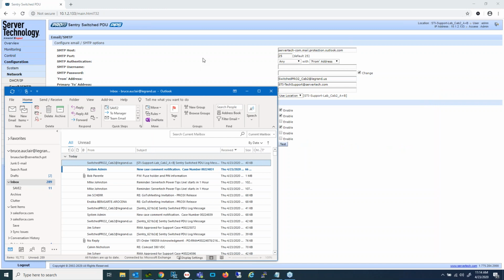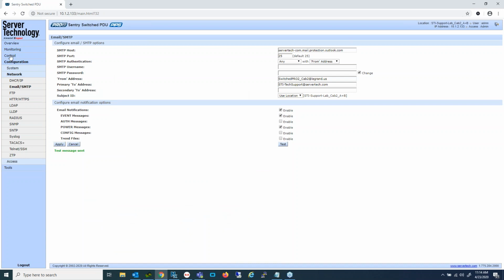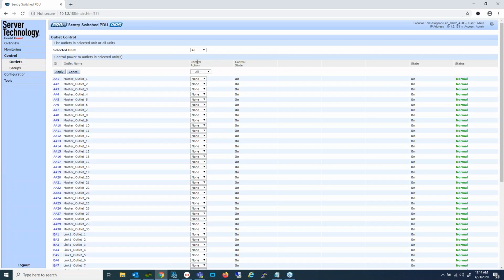So then how do you know if an event is actually going to result in you getting notified by syslog, SNMP, or email? There's a couple of different ways. One, in the case of a switch PDU, which is what I have in my office, a very simple method is to just switch an outlet on or off or reboot it. You want to make sure it's an outlet that's not in use, or choose a different way. I am going to reboot outlet number 1 on that PDU.